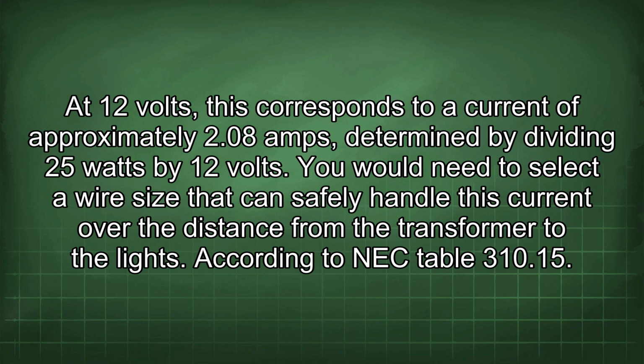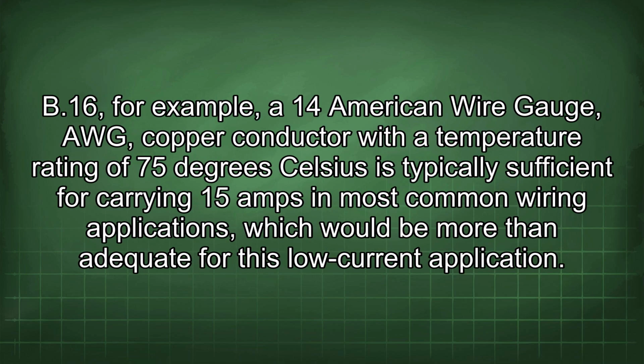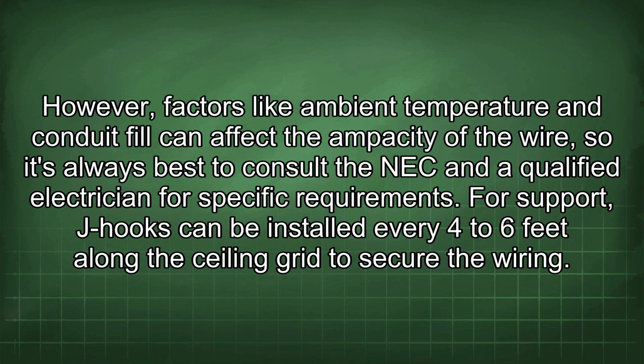to the lights. According to NEC Table 310.15(B)(16), for example, a 14 AWG copper conductor with a temperature rating of 75 degrees Celsius is typically sufficient for carrying 15 amps in most common wiring applications, which would be more than adequate for this low current application. However, factors like ambient temperature and conduit fill could affect the ampacity of the wire, so it's always best to consult the NEC and a qualified electrician for specific requirements.